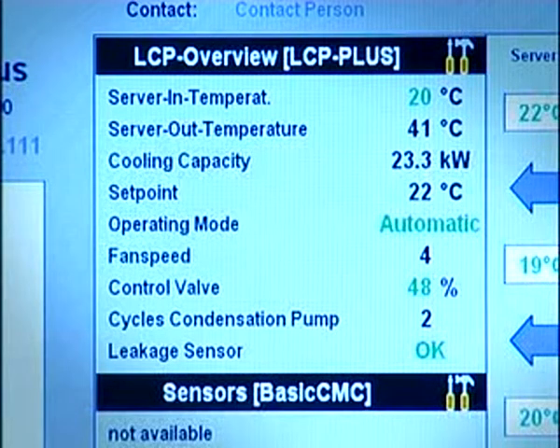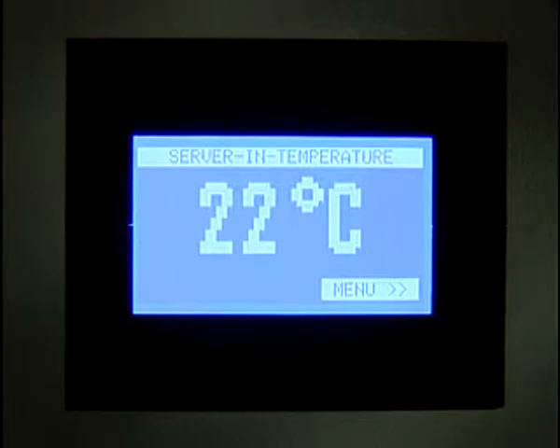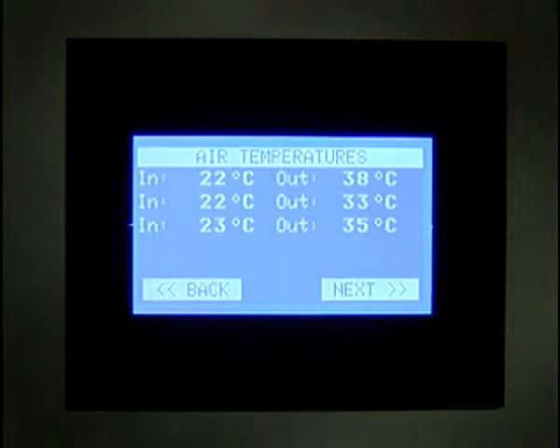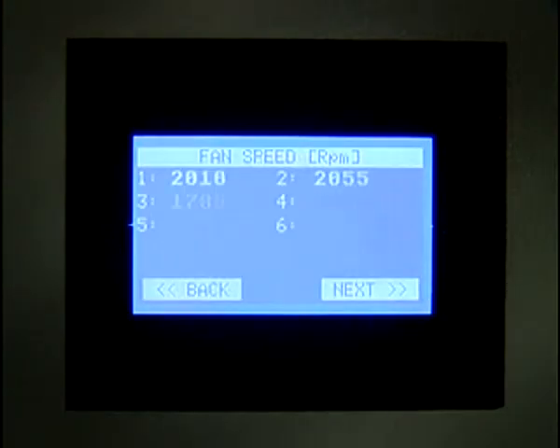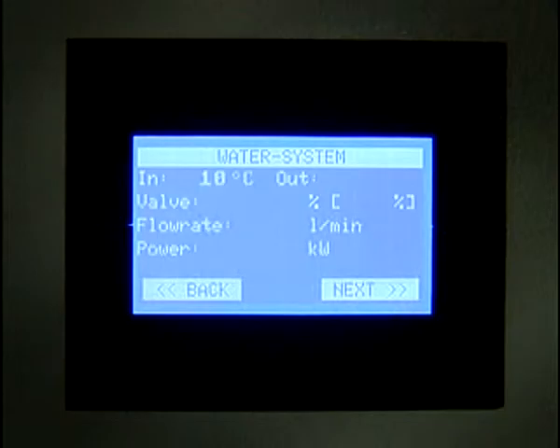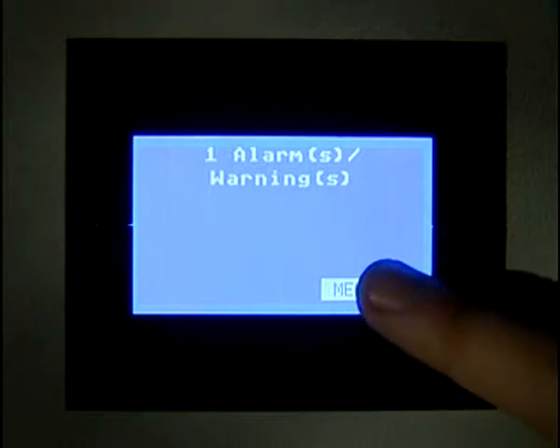Cooling is only one part of the functionality of the LCP Plus. Remote monitoring and control is essential so you understand what is going on within your high-density enclosure and can also adjust any parameters to suit individual applications. A backlit touchscreen LCD permanently displays the average server inlet air temperature so you can get an immediate indication of cooling. This screen can be interrogated so you can see fan rotational speeds, inlet and exhaust temperatures, water flow, inlet and outlet water temperatures, and of course, any alarm activity.